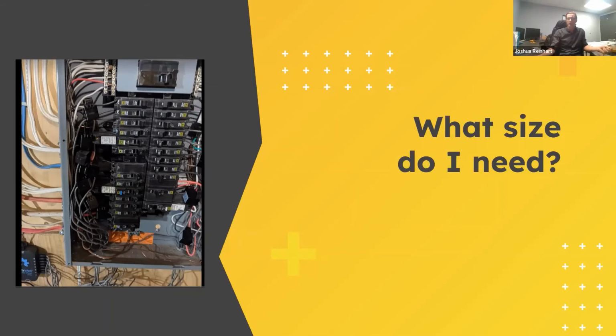If you have an existing 100 amp service and your panel is just too small, you might not need a service upgrade. When you change out that panel, think about getting a tub, or box, for the panel rated for 200 amps. You can always put in a 100 amp main breaker, which you can see at the top of this panel, and keep the tub rated for 200 amps, so down the road when you plan to do that upgrade, you don't need to change the panel again.